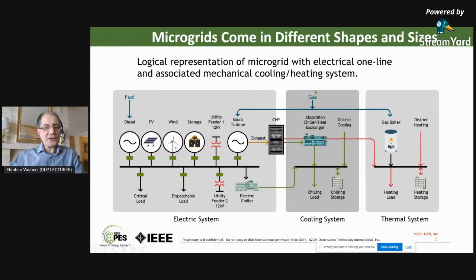Now let's go to the cooling part of the microgrid. The microgrid can have some cooling requirement. Where does that cooling come from? You could have an electric chiller, as we just discussed, or additionally or optionally, an absorption chiller that uses exhaust from the micro turbine to create cooling.